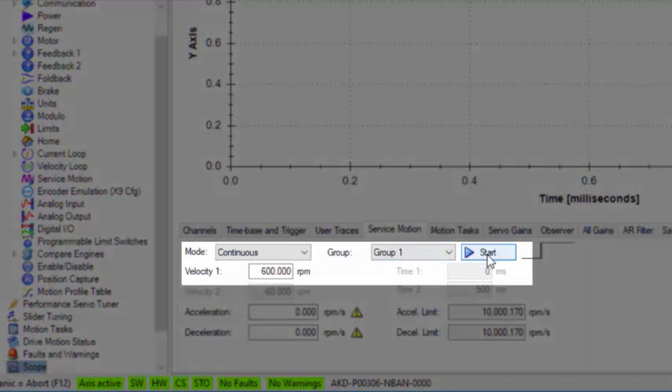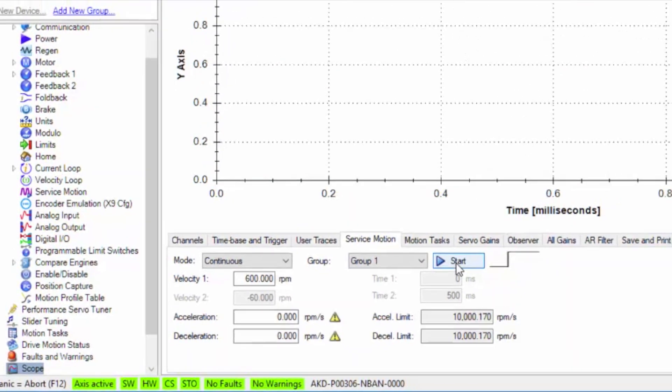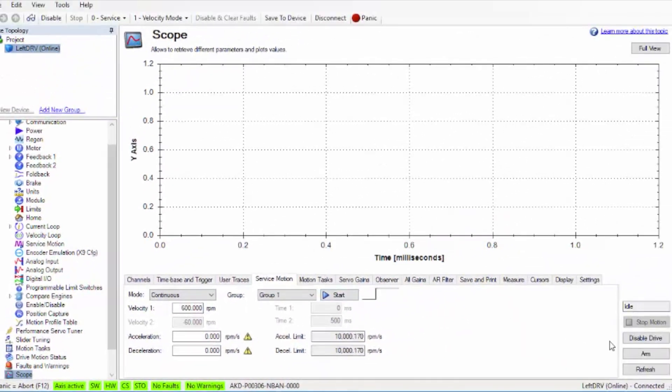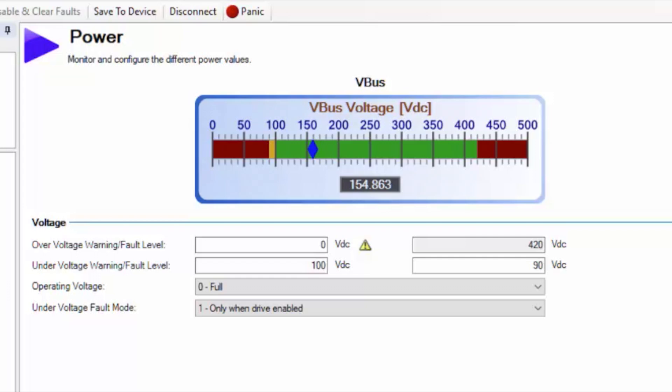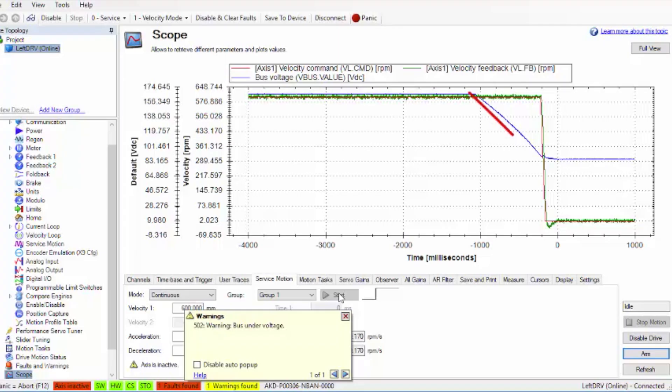The motor is running at 600 RPM, the scope is armed, then the line voltage is cut off. The bus voltage drops down to 90 volts DC and the drive fault occurs. The scope is triggered.